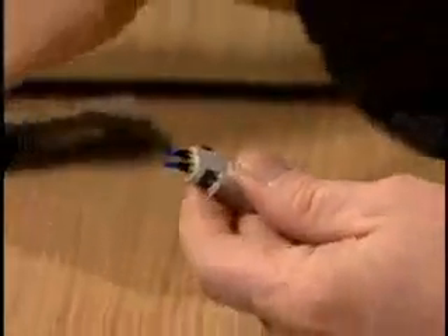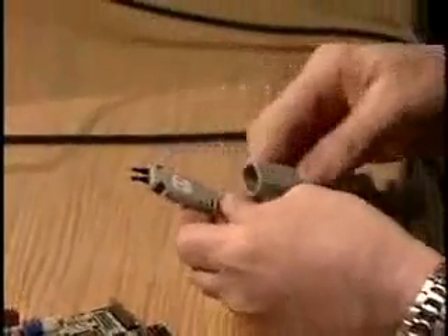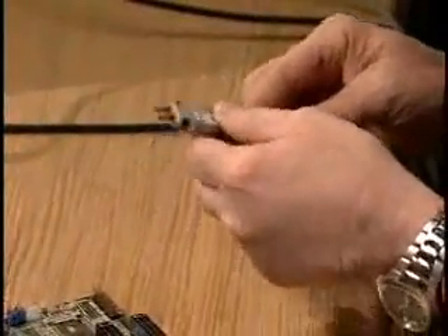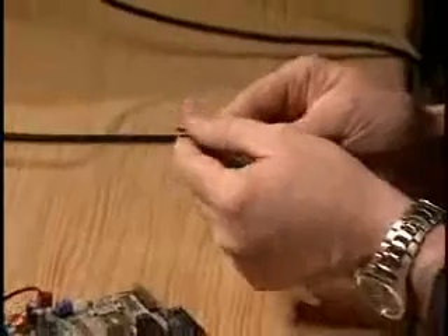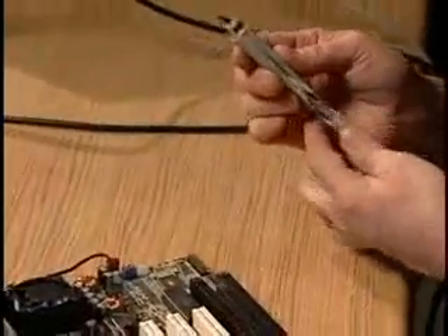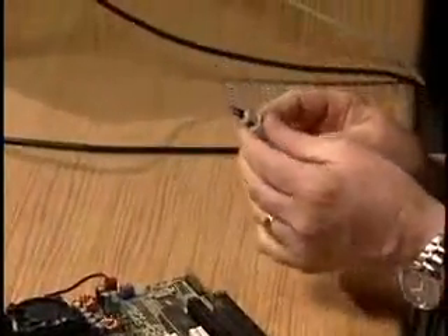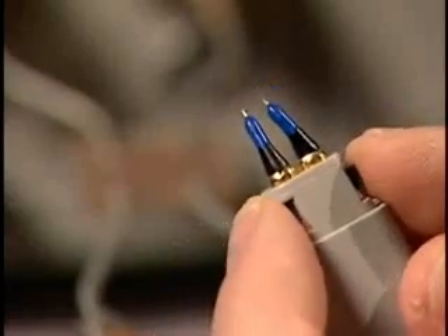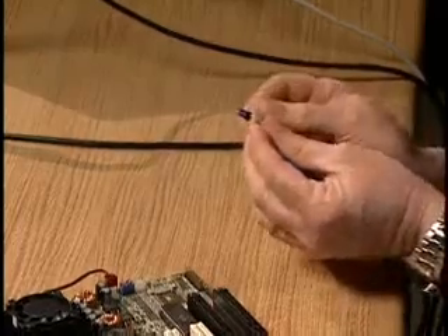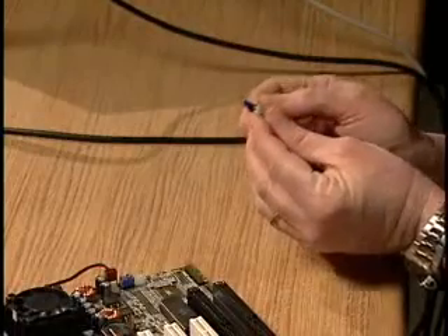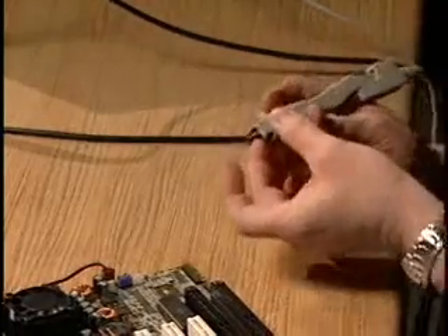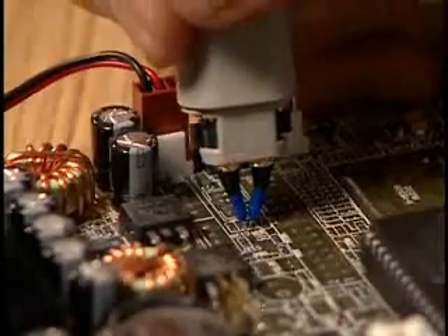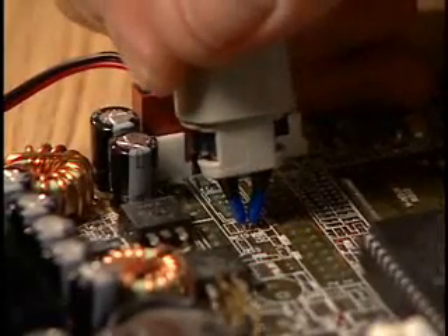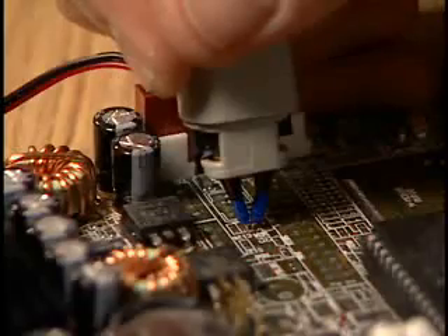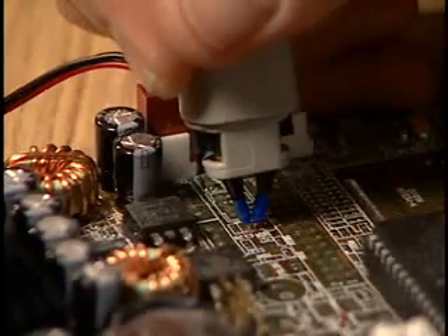To enhance the usability of this probe head and amplifier assembly, you can also attach the ergonomic probe sleeve that joins these two components together, making it easier to hold in your hand as a single unit. Using the levers on the sides of the browser probe head allows you to easily adjust the probe tip span to the correct spacing to fit the test points of your device under test. When connecting to a device's test points, we recommend you connect at a near perpendicular angle, then apply enough vertical force for the spring compression of the probe tips to depress.